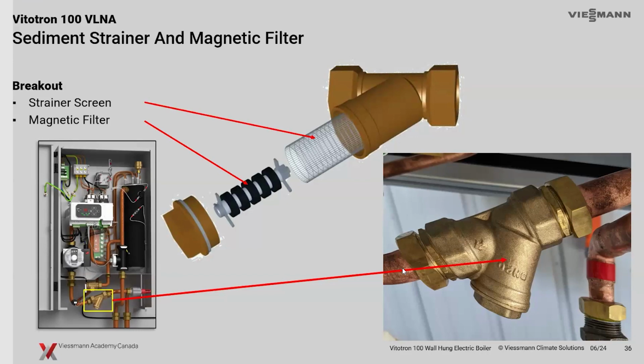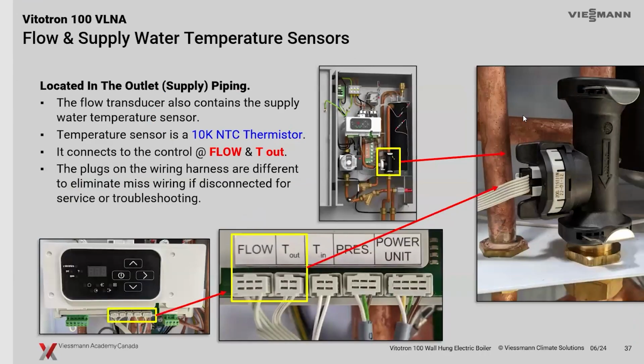That's going to essentially save things like the pumps, and the debris attaching to the elements inside of the heat exchanger when they're hot. That stuff is what scales up and then starts to shorten the life of your electric boilers. So again, having the strainer in there is very helpful to avoid a lot of that. But again, it's a maintenance thing. So once we install this, if you start dealing with high pressure drops and issues with pump flow, a good spot to start looking is to open up this little cap and have a look at how much debris is stuck inside that little strainer. So just keep in mind that it's built in, and that will be a service item to look at in the future.